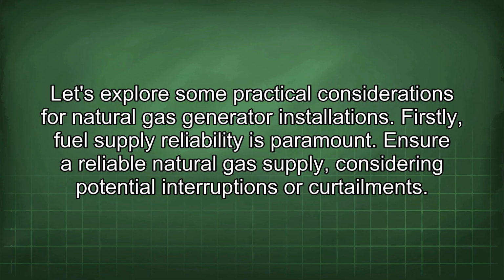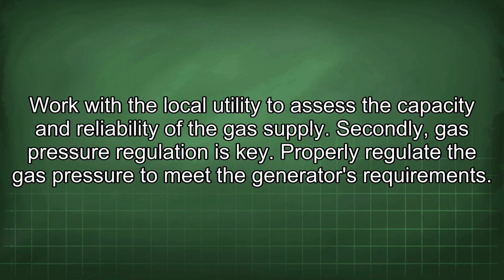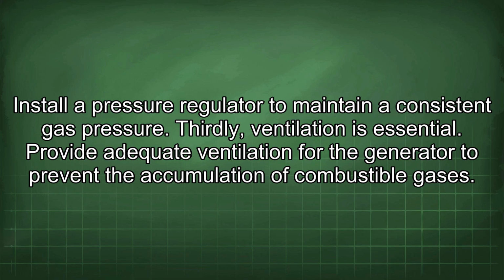Let's explore some practical considerations for natural gas generator installations. Firstly, fuel supply reliability is paramount. Ensure reliable natural gas supply, considering potential interruptions or curtailments. Work with a local utility to assess the capacity and reliability of the gas supply. Secondly, gas pressure regulation is key. Properly regulate the gas pressure to meet the generator's requirements. Install a pressure regulator to maintain a consistent gas pressure.